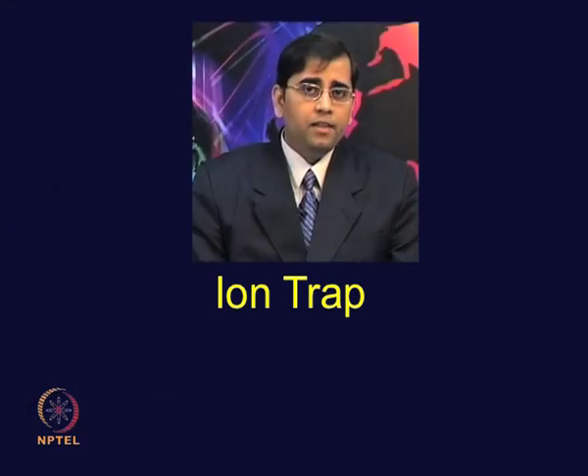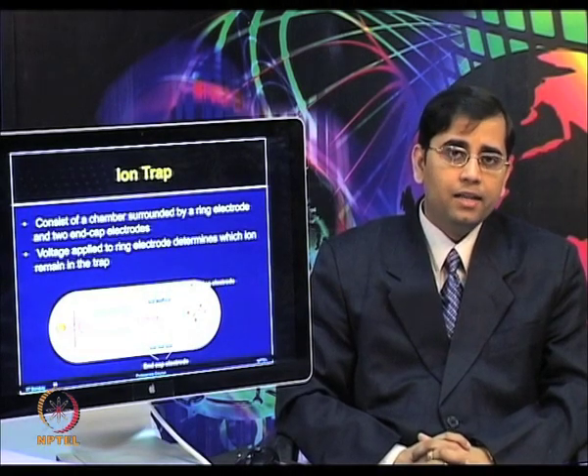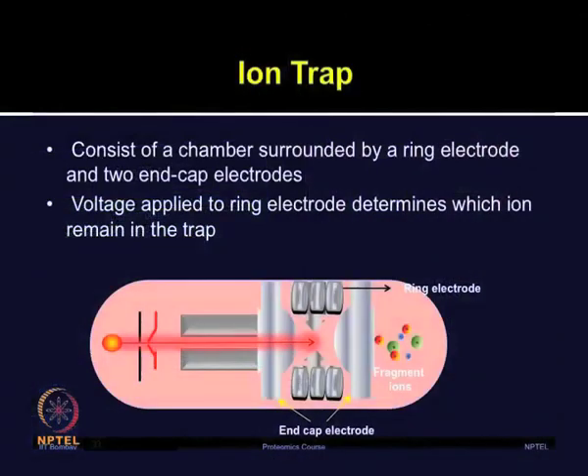Another important mass analyzer is the ion trap. The ion trap traps ions using electrical fields and measures mass by selectively ejecting them to a detector. It consists of a chamber surrounded by a ring electrode and two end cap electrodes. The voltage applied to the ring electrode determines which ions remain inside the trap. Ions above a threshold m/z ratio remain inside the trap and others are ejected through a small hole. The ion trap can theoretically provide MSn analysis and also serve as a mass filter.